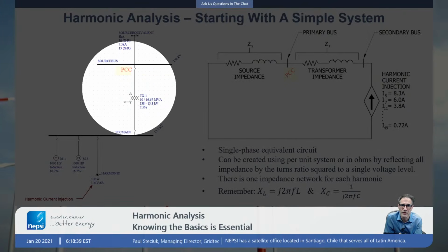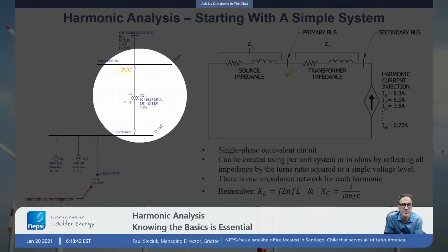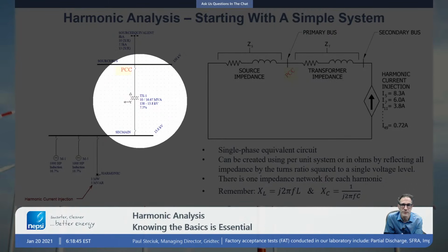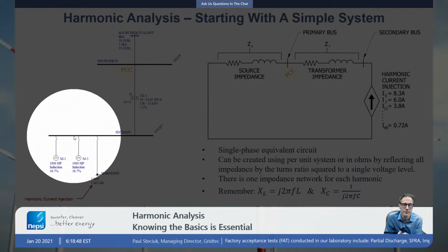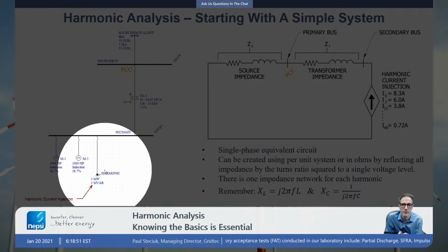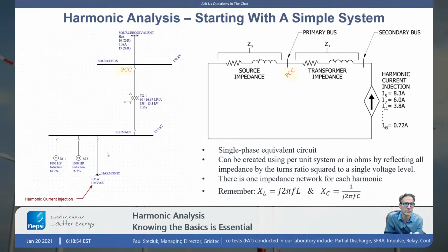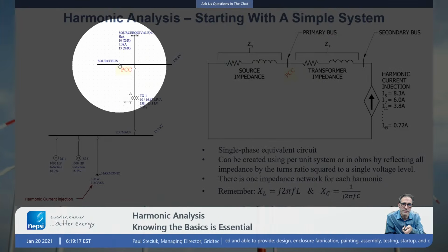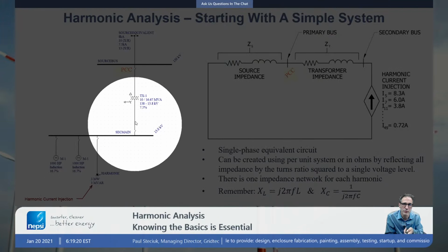We have an input transformer TX1 here, and in this case it's 10 MVA, and it has a 7.5% impedance. And then down here we have just a very simple bus bar, 13.8 kV, and we have some harmonic producing loads. Those harmonic producing loads might be an LCI drive, it might be a VFD drive, it could be rectifiers, it could be wind turbines, solar inverters, you name it, whatever produces harmonics could be that. We've taken all the harmonics within the plant and we've summed it up and put it into one load in this particular model.